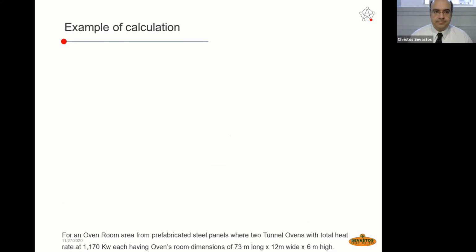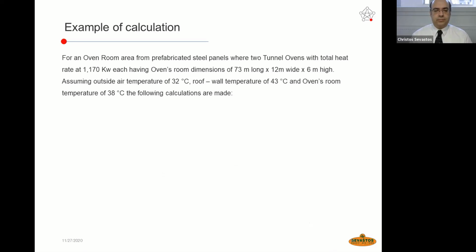Now let's go to the example. Let's assume that we're going to have an oven room, which is constructed by prefabricated steel panels, having 2 tunnel ovens with total heat rate of 1,170 kilowatt each oven, and having, let's say, room dimensions of 73 meters long, 12 meters wide, 6 meters in height. Assuming that the outside air temperature is 32 degrees Celsius, roof and wall temperature 43 degrees Celsius, and oven room temperature of 38 degrees Celsius, we have the following calculations.